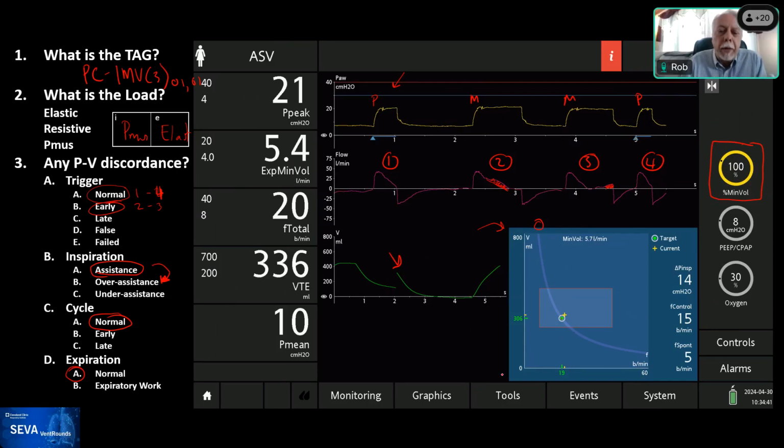And that's the rectangle. That is the high and low permitted tidal volume and the high and low permitted respiratory rate by the built-in expert system, and that's why we call it intelligent.